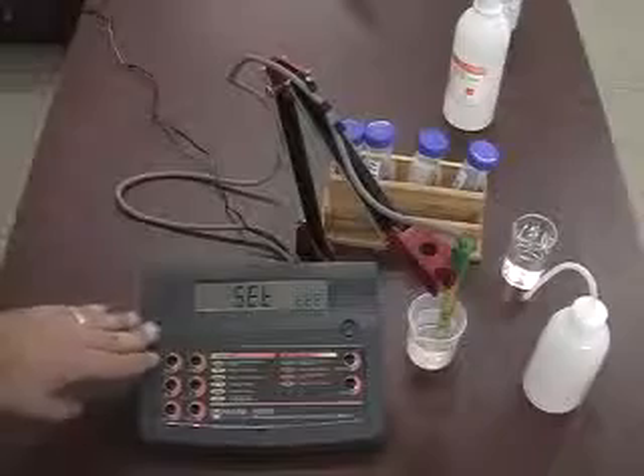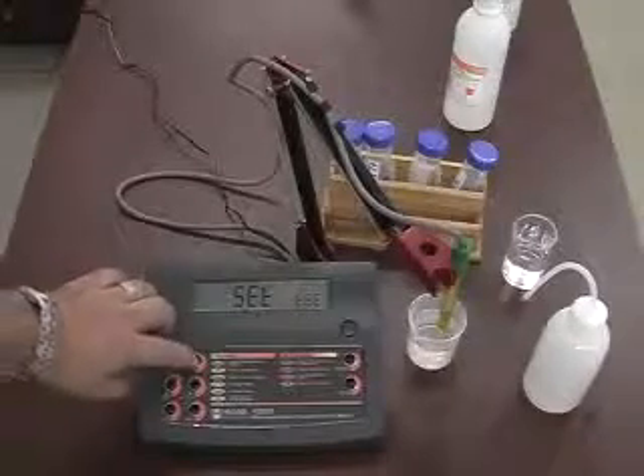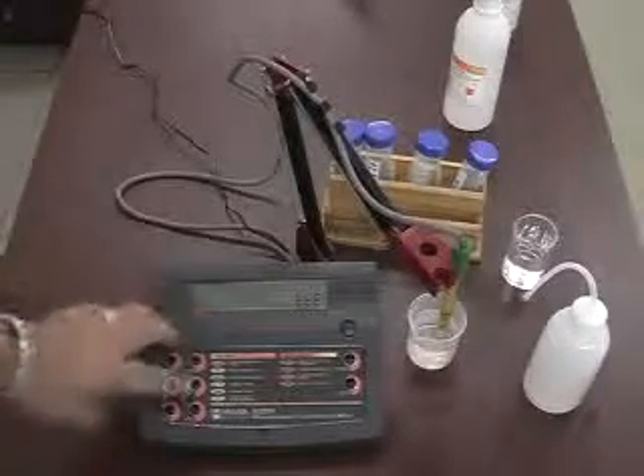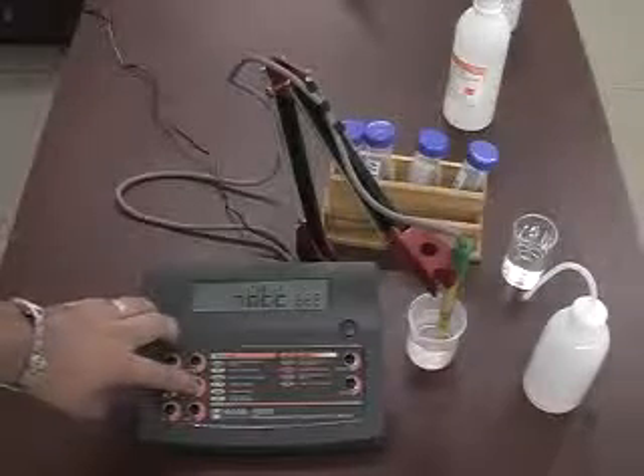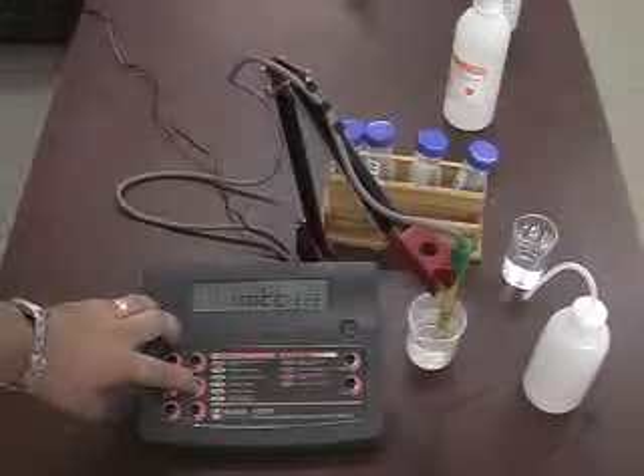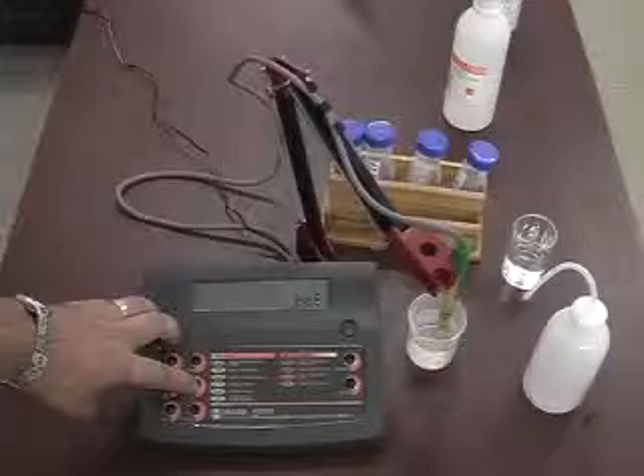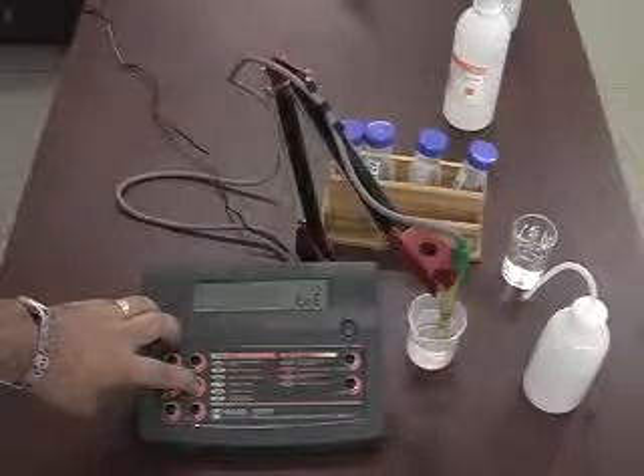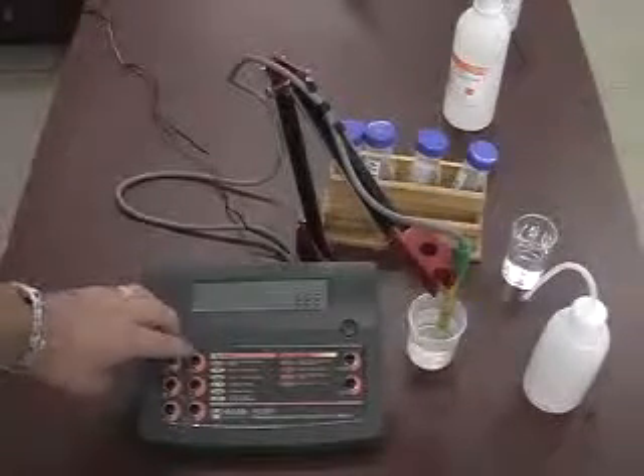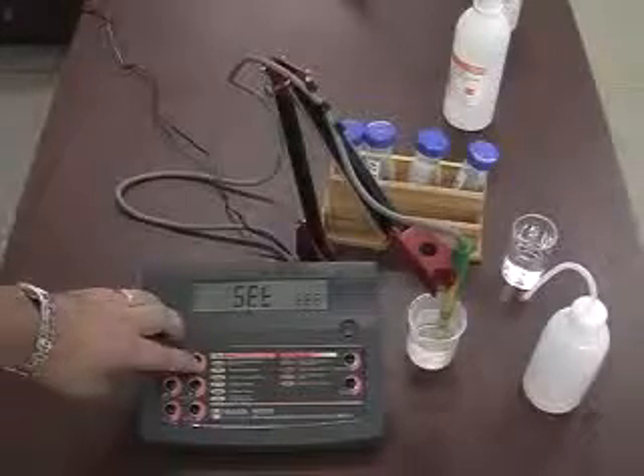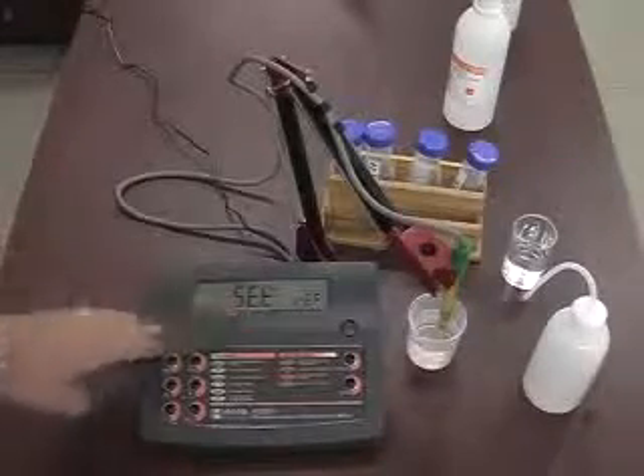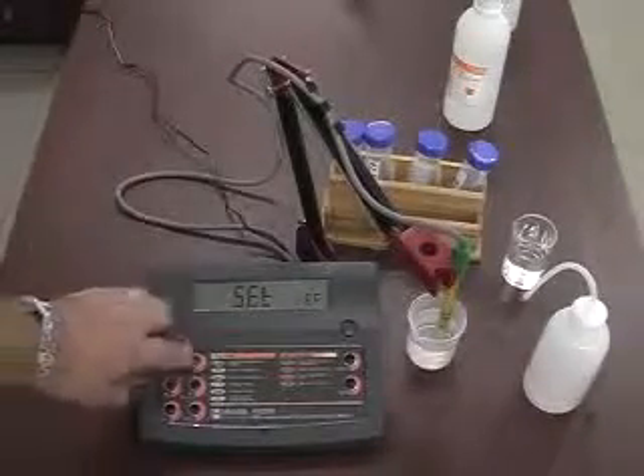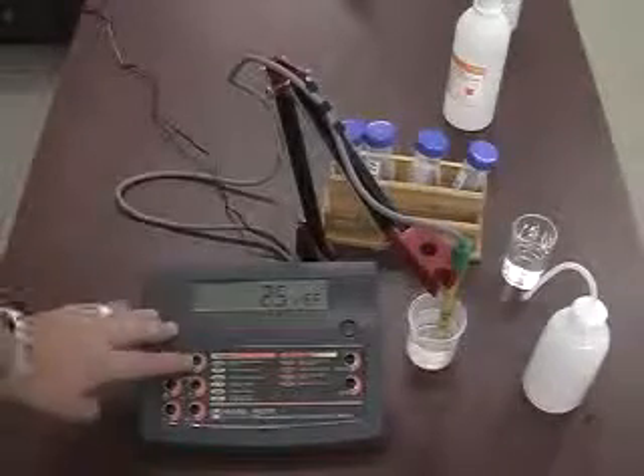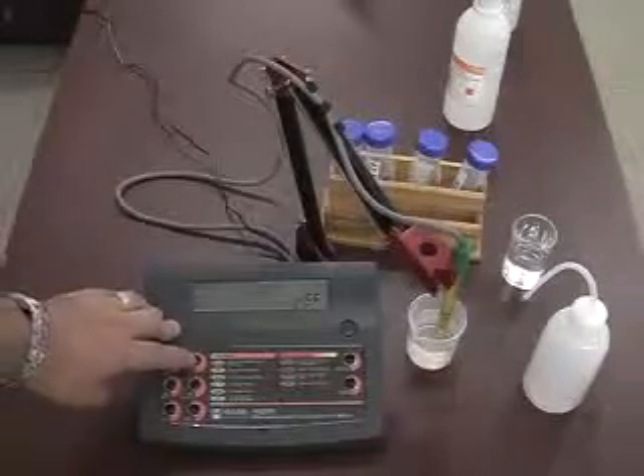This is for what type of temperature compensation we'd like to have. Pressing confirm, we can change it from automatic temperature compensation to no temperature compensation to manual temperature compensation. Since I like automatic temperature compensation, I leave it set on that. The next is the reference temperature that we base on. Most meters are programmed automatically at 25 degrees Celsius.